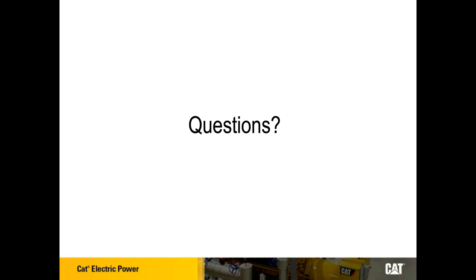Steve, I might chip in on that too. On the question about fuel for system resiliency, I think it depends on location, like you said, addressing the availability of natural gas. We're seeing some systems called microgrid systems in areas that have utility power, usually a system that can connect or disconnect from the utility. In coastal areas, we'd suggest looking at natural gas, since Superstorm Sandy, Hurricane Katrina, and Harvey demonstrated that after a major weather event, gas pipelines are usually unaffected, but roads are blocked and closed so diesel can't be delivered to refill tanks. For those more unconventional microgrid applications versus something at a remote site, we might suggest looking at natural gas.